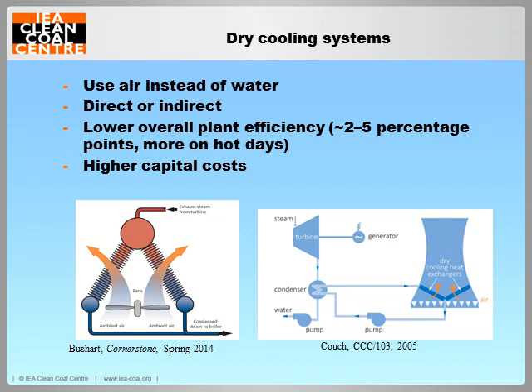Direct cooling uses a large standalone air-cooled condenser. Steam exiting the turbine is condensed within fin tube heat exchangers, which are externally cooled by ambient air. The fin tubes are commonly arranged in an A-shaped frame over a forced draft fan, which is shown in the figure on the left. The system can consist of several rows of heat exchanger cells.